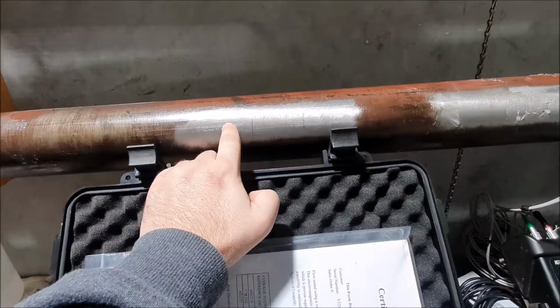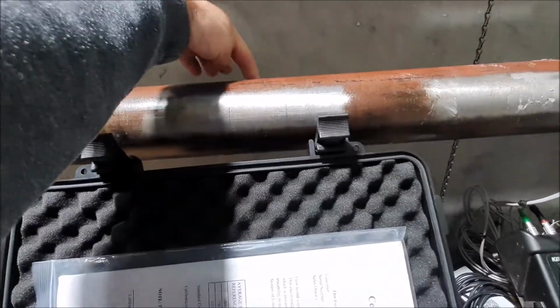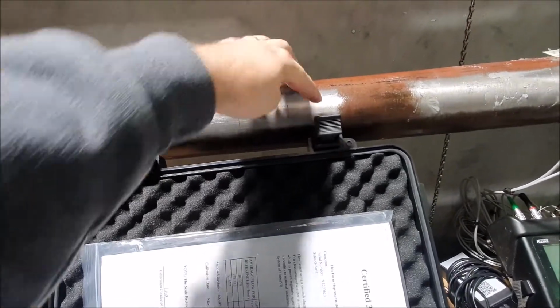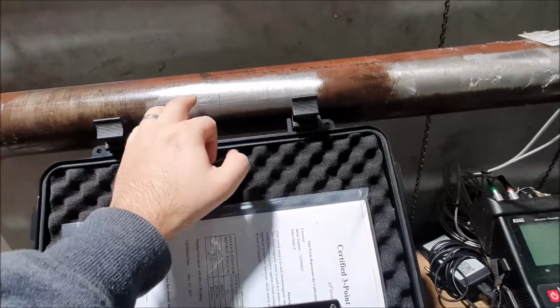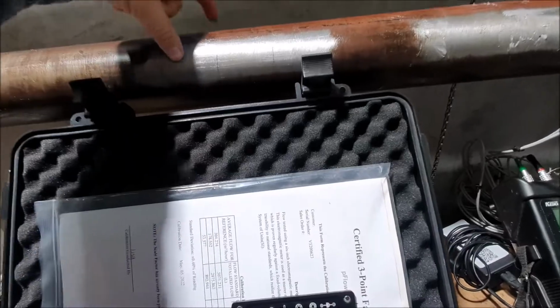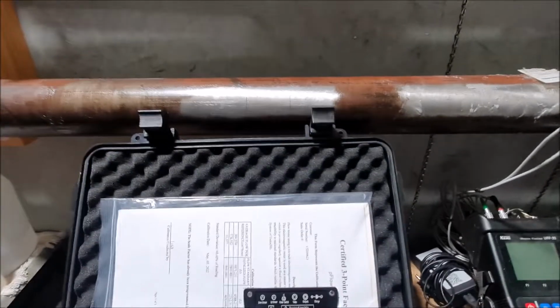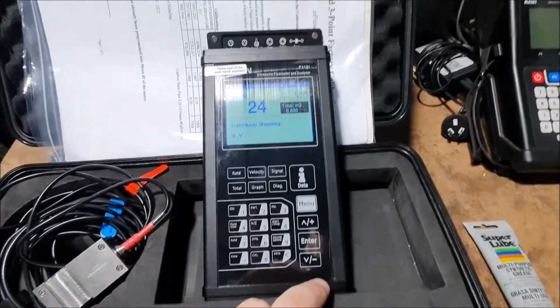Basically, your signal will bounce from one transducer off the back of the pipe and into your transducer again. But there are other mounting methods like Z, where it doesn't bounce, and you'd have your transducers on opposite sides of the pipe. So you'd have one here and one on the back. But in this demo, we're just going to use the common V. So we need to change that.